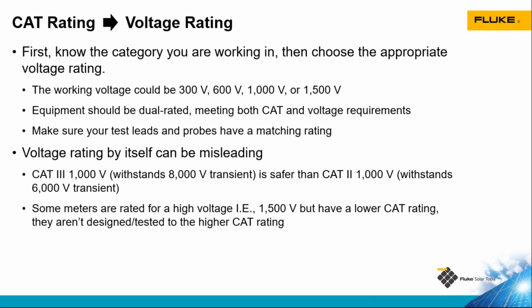Just looking at the voltage rating itself can be a little misleading. Here the example is a category 3 1,000 volt rated tool is designed to withstand 8,000 volt transients, where a category 2 1,000 volt rated tool is only designed for 6,000 volt transients. So even though they're both 1,000 volt rated tools, because the category rating is different, their ability to withstand transient voltage spikes is different as well.